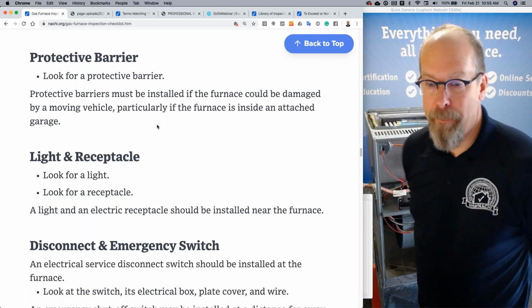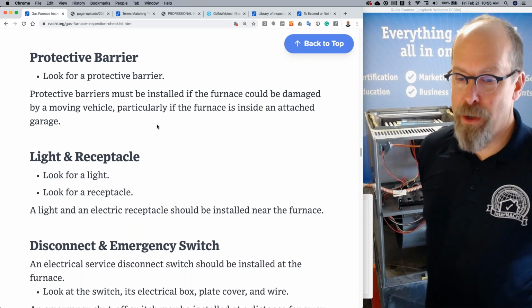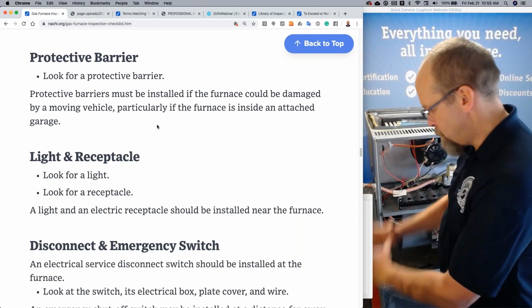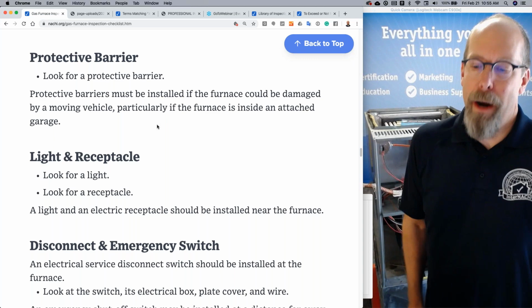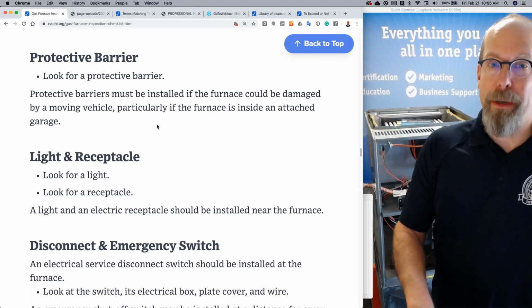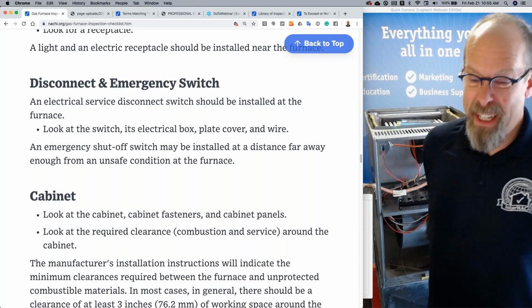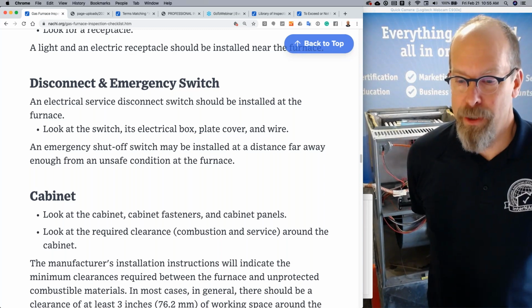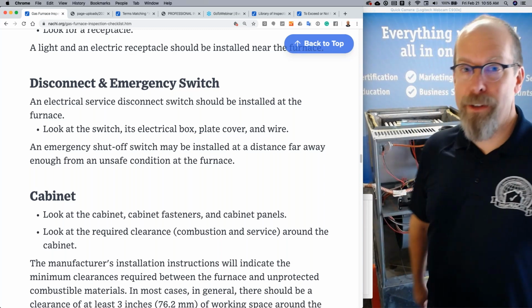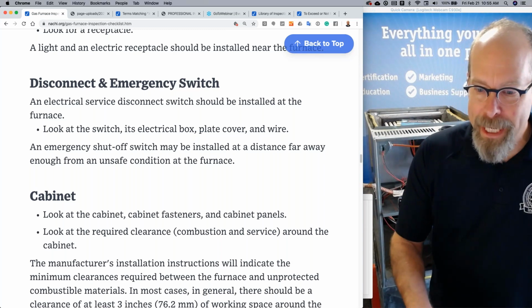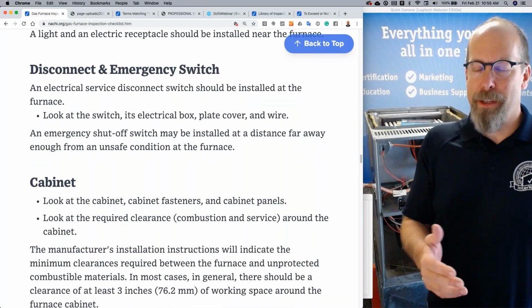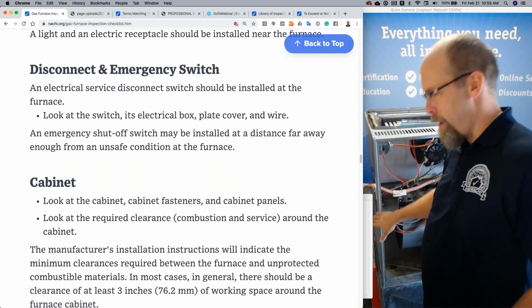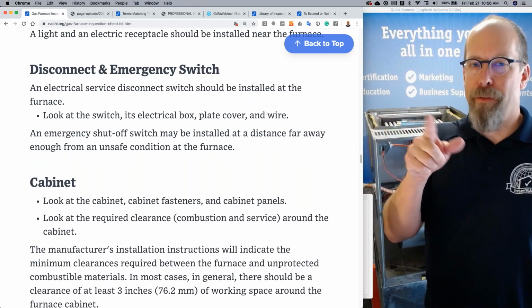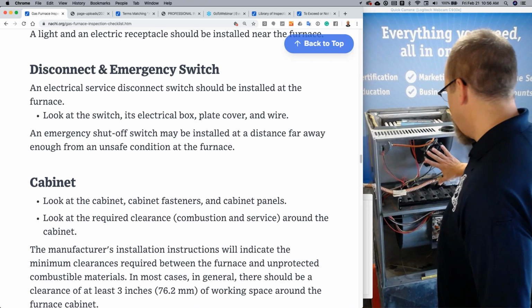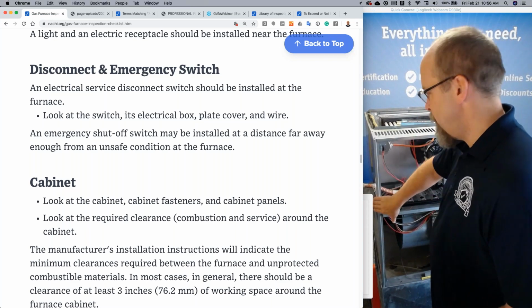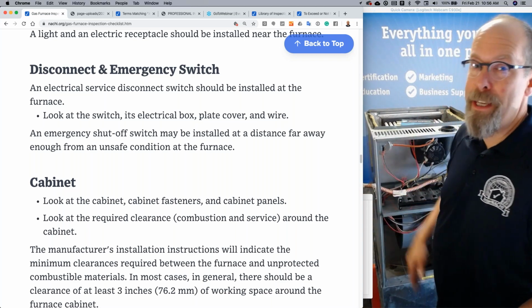So protective barrier. Protective barriers must be installed if the furnace could be damaged by a moving vehicle. So you've got those posts in the garage, right? Or any kind of barrier. A light and receptacle should be installed near the furnace. There should be a disconnect and emergency shut-off switch. I use the disconnect switch. As part of my inspection process, I turn the system off, go to the thermostat, call for heat, come back, remove the cabinet panel front, turn the service switch on, and look at the sequence of operation.